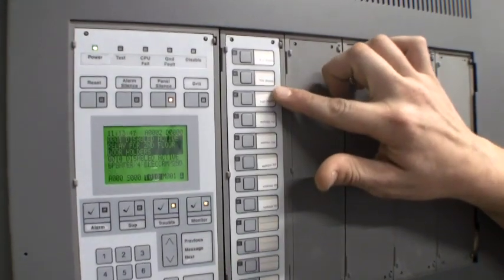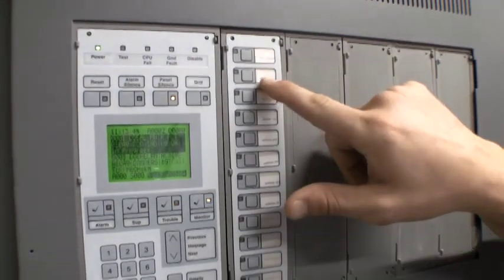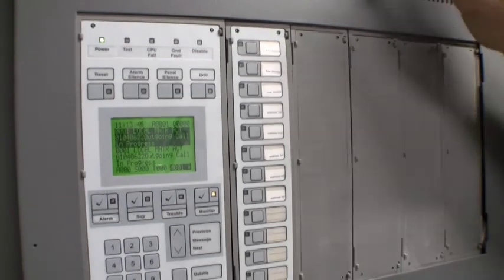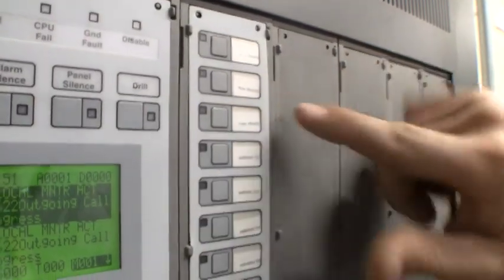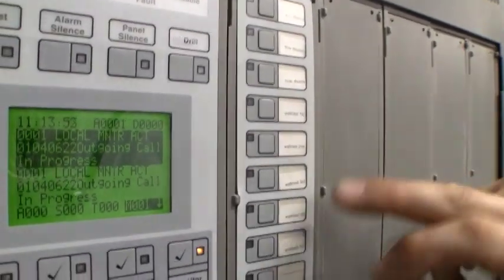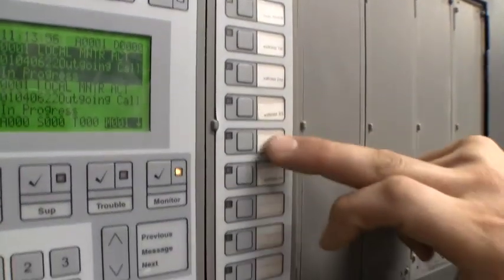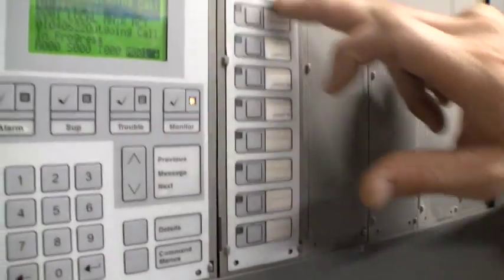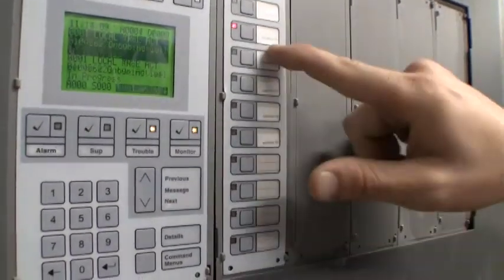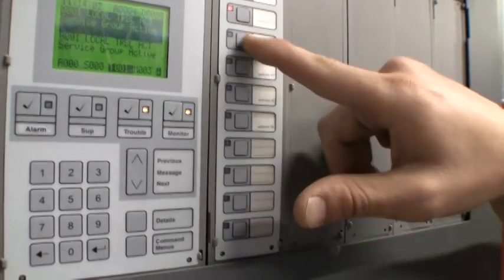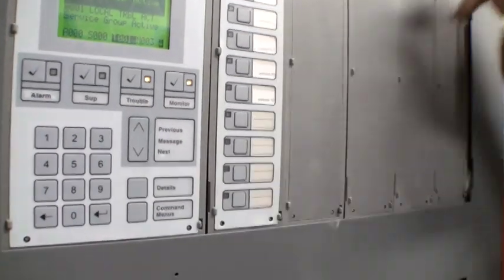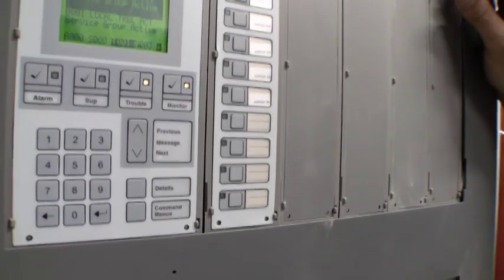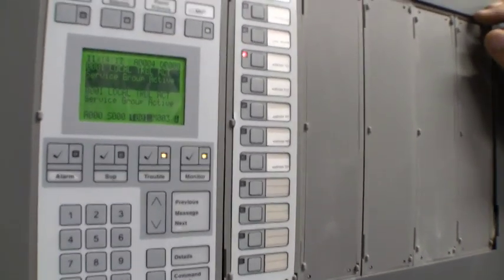We have one switch for the sprinklers — it'll disable any water flow or sprinkler. We have one for HVAC disable, and then we have one that'll break it down floor by floor, putting the first floor, second floor, or third floor into a test procedure. That way when you hit a device on that floor, your strobe will flash for ten seconds, letting you know that you've got the alarm, and it'll clear itself out.